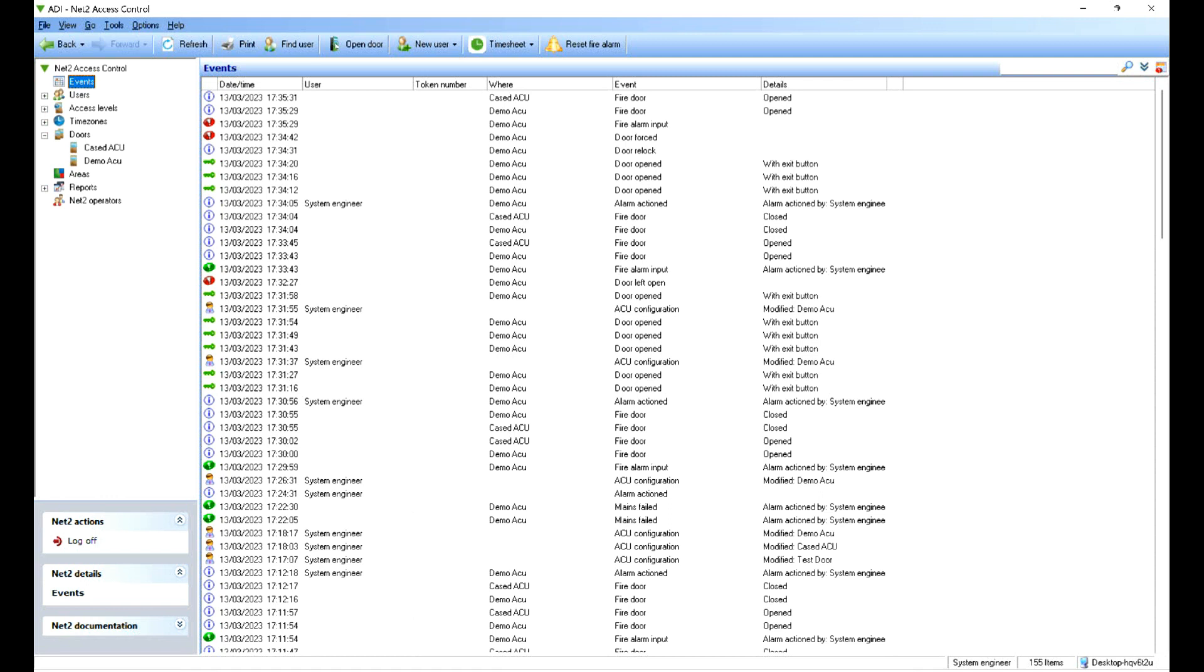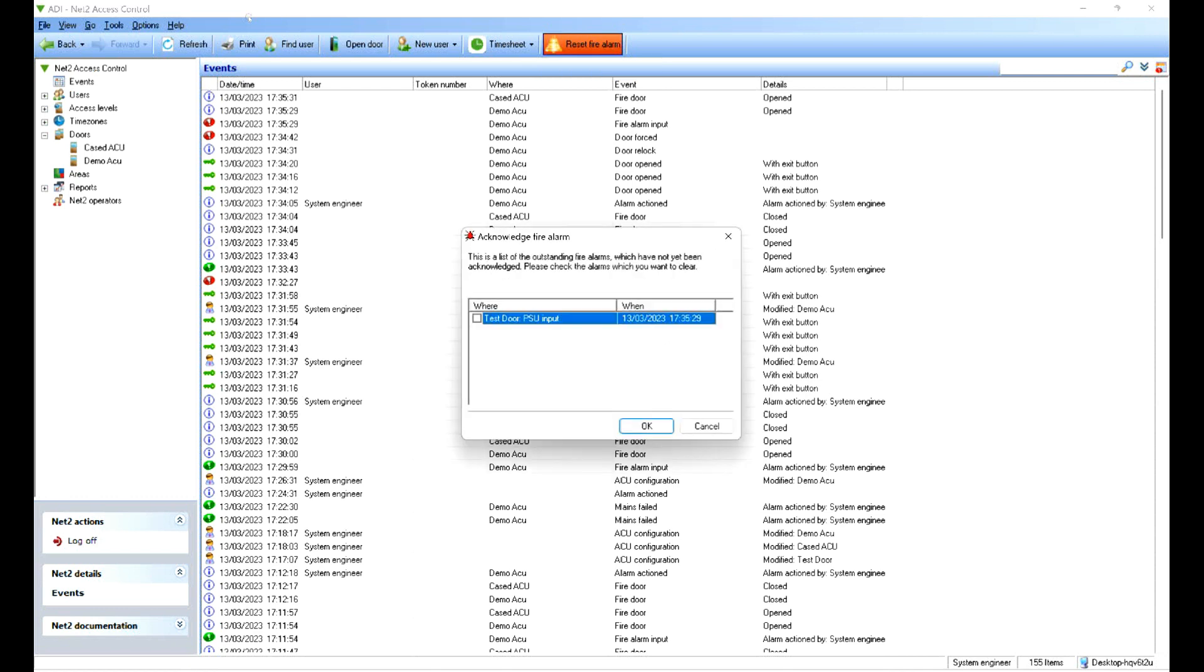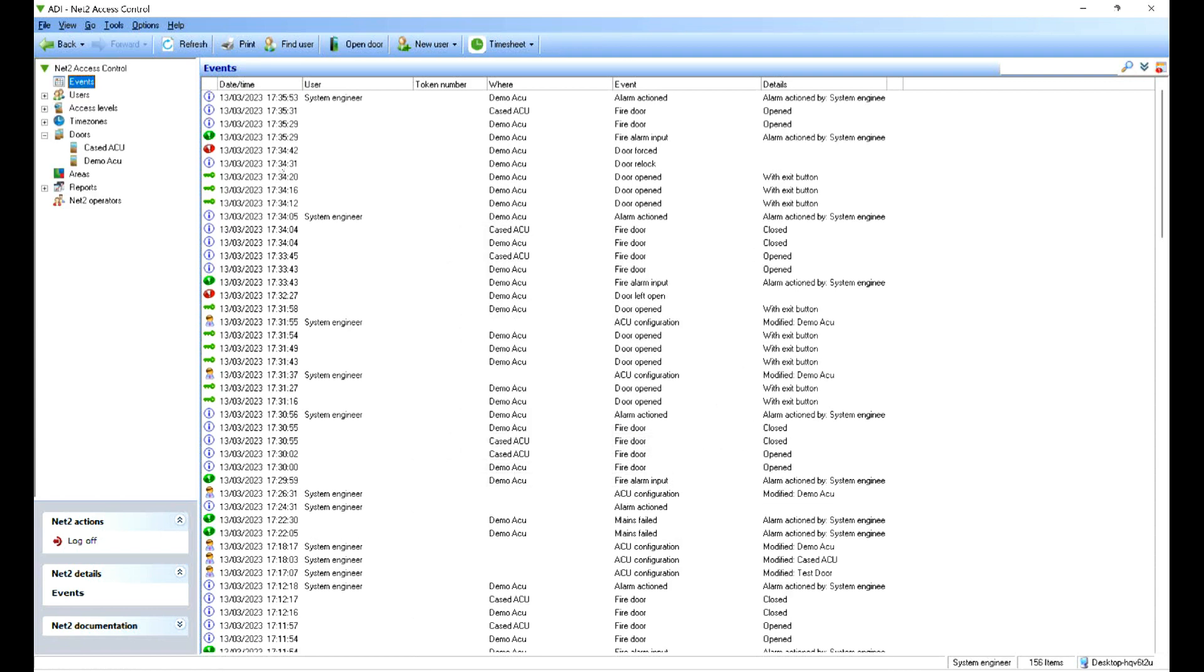Now if I—above we can see we've got an icon, fire door reset. If we click that, we can then choose the input we want to reset. Select that, press OK, and that will then lock the doors and put them back into normal access control mode.